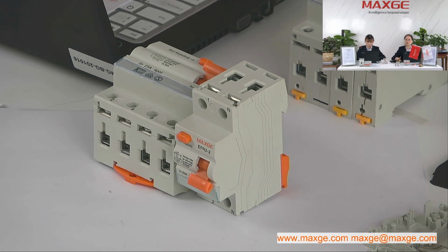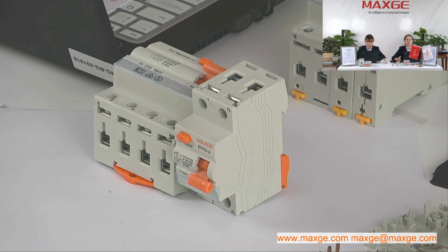Here is our terminal for RCCB. It has a large terminal size of 35 square millimeter, which is suitable for both copper and aluminum cable. Here we can use both pin type and fork type on both sides.